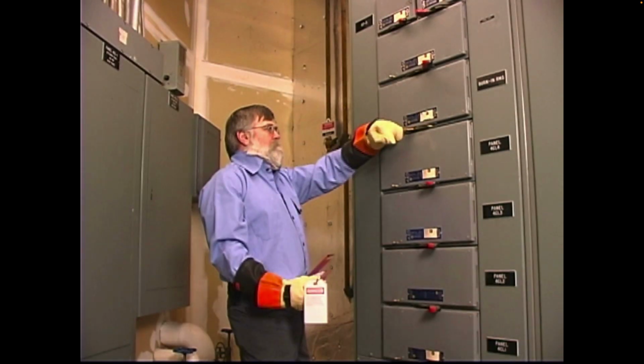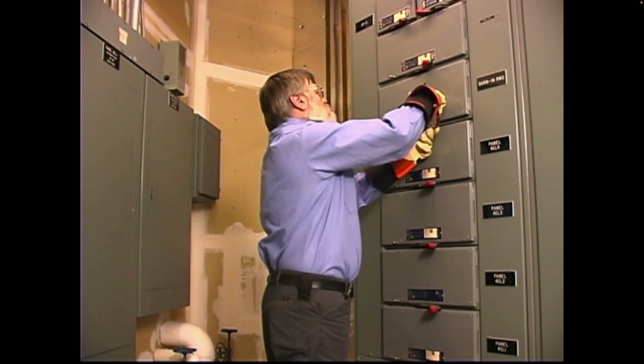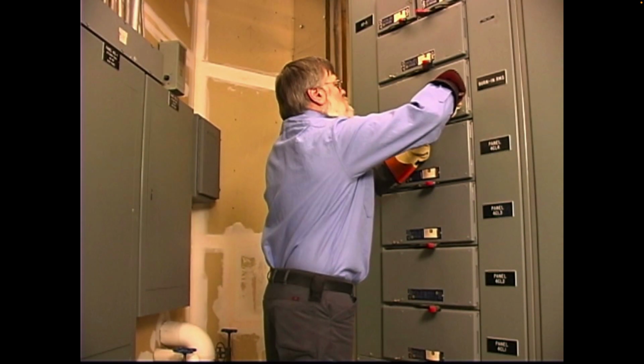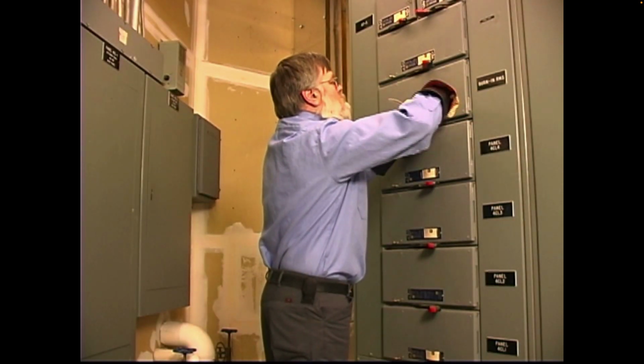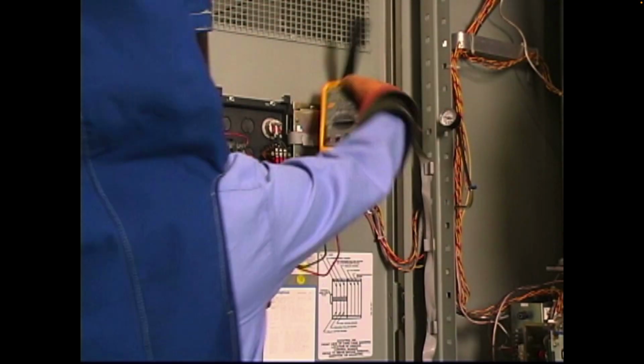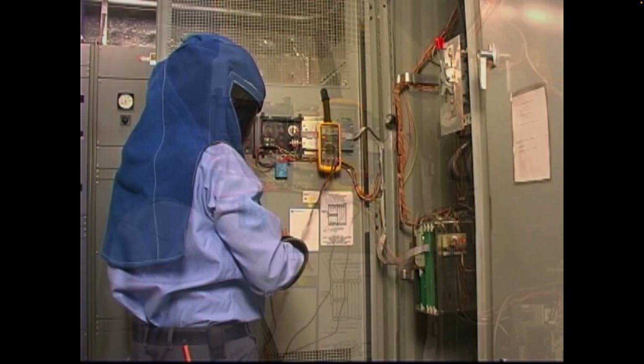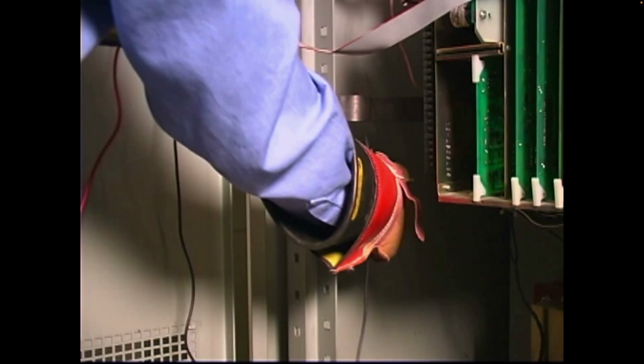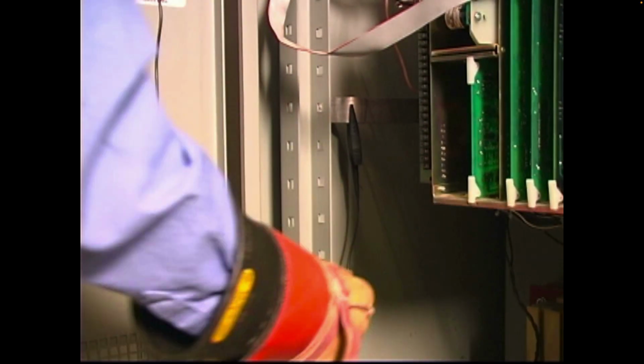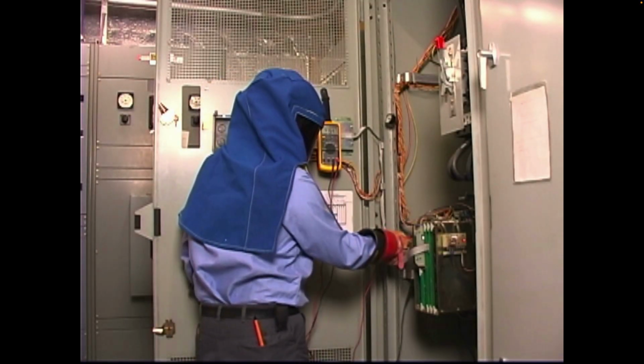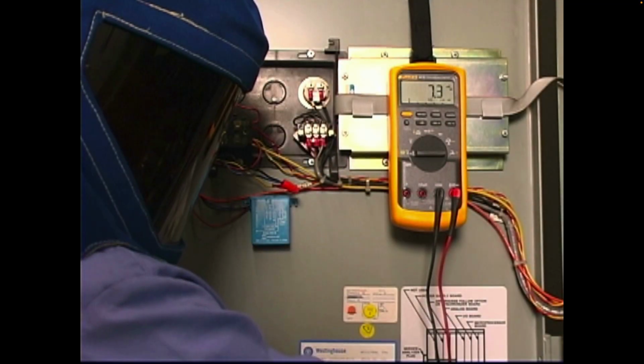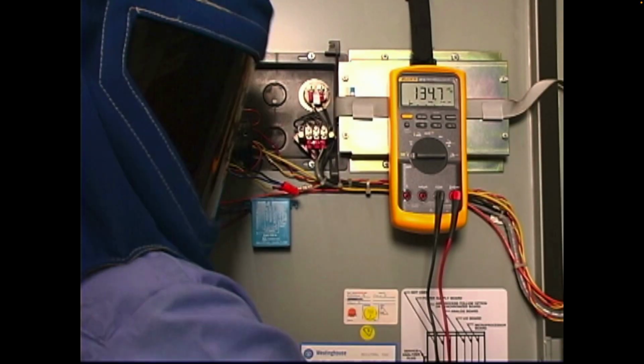Whenever possible, work on de-energized circuits and always follow proper lockout-tagout procedures. When taking single-phase measurements, always connect the grounded lead first, the hot lead second. After taking your reading, disconnect the hot lead first, the grounded lead second.